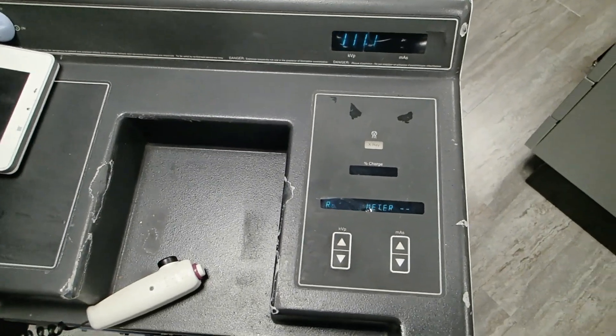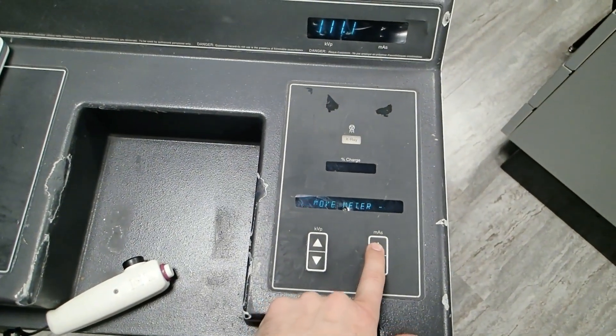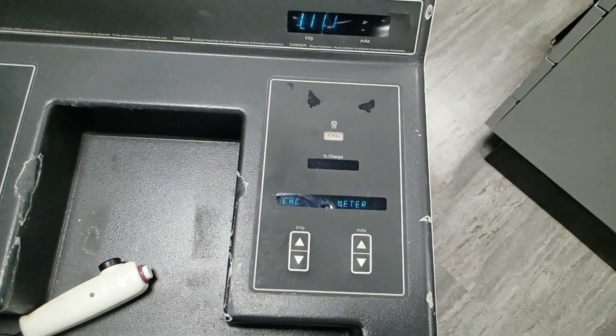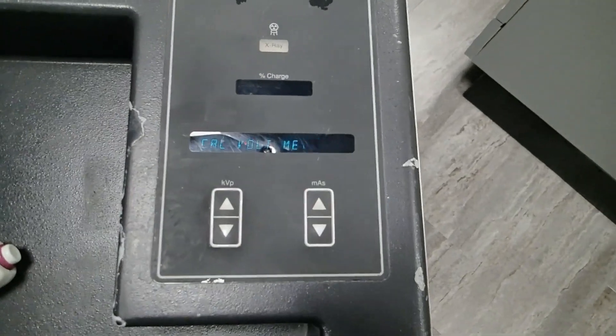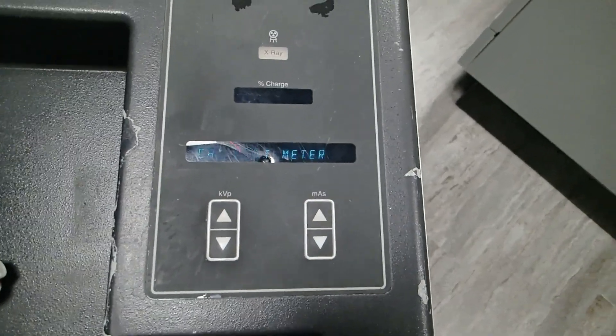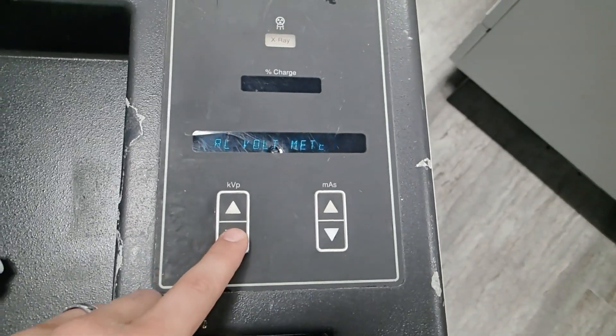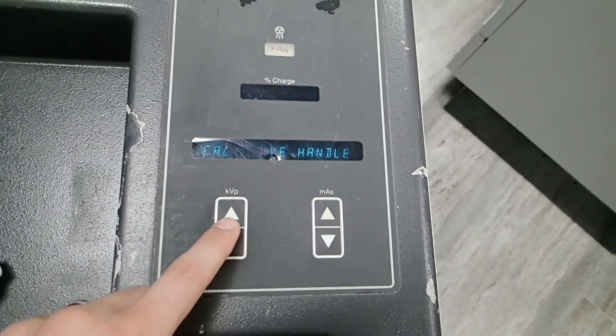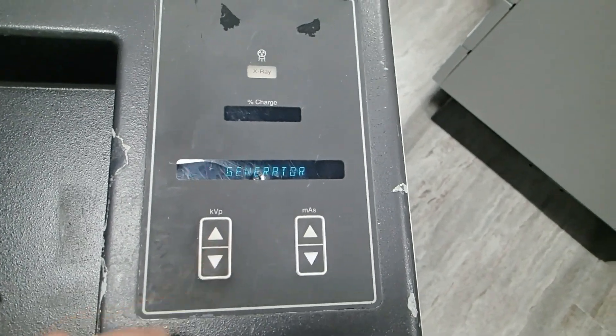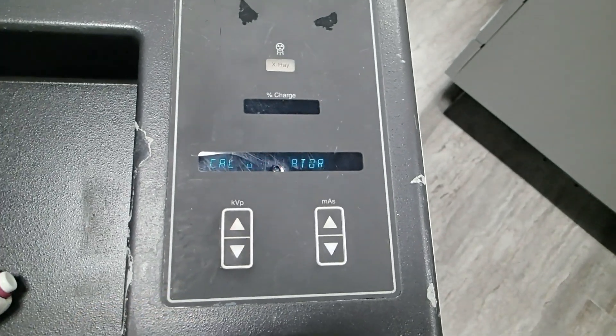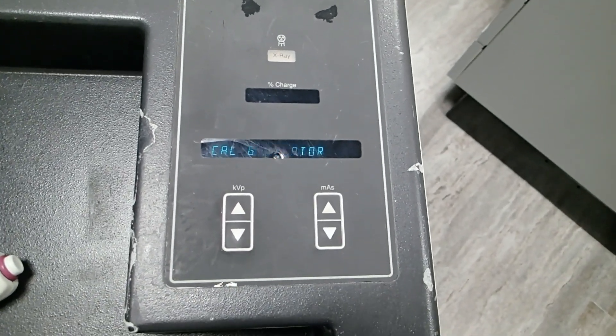Now I can remove the meter. Now that the meter is removed, I'm going to go ahead and hit the MAS up button. Now it brings me back to our original menu. What I want to do is calibrate the generator now. So I'm going to go to calibrate generator, hit MAS down.